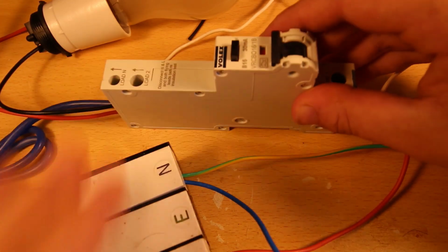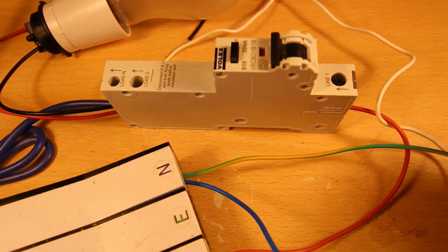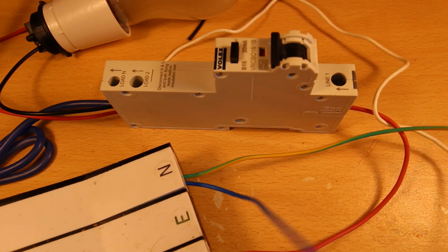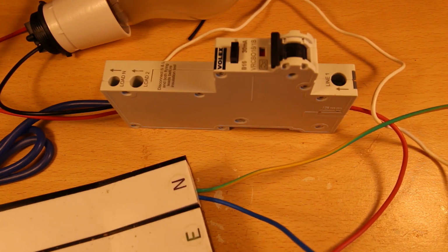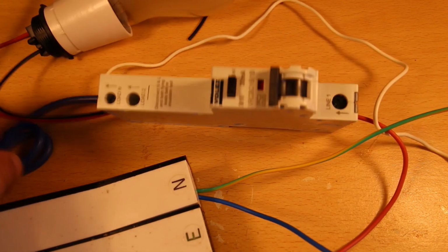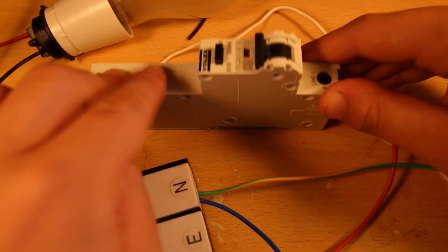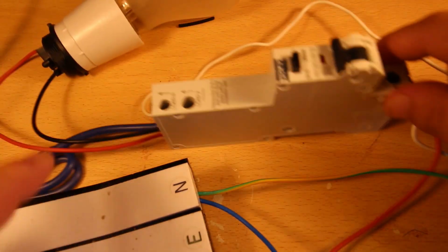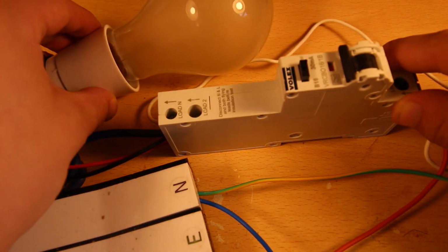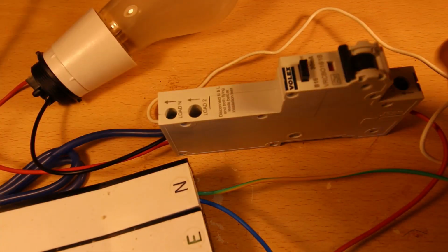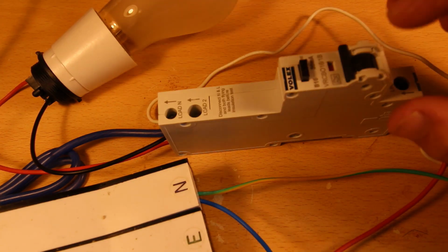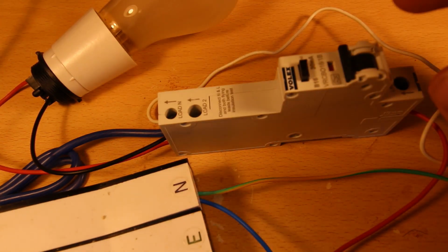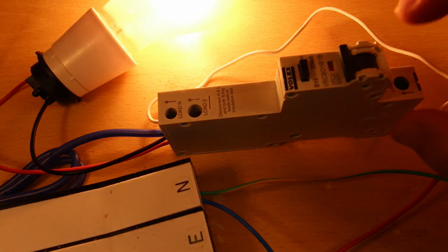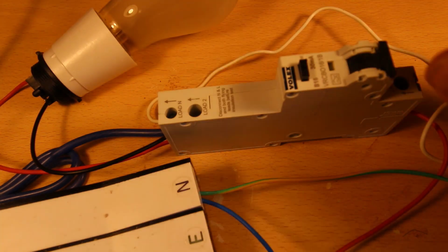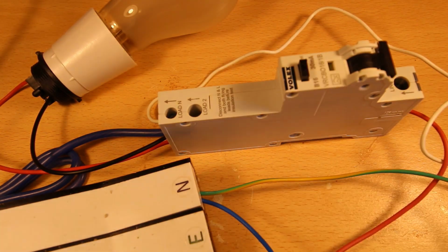So this RCD has the feed coming from the grid in, it has its neutral from the main earth terminal here, coming out here, goes into the input neutral for this. It has its incoming live, and then the outgoing from that goes to my load, which is this 150 watt light bulb. When I then power this on, to prove to you that the RCD does actually work, I will press the test button, and see, it does indeed trip. So this RCD does work.